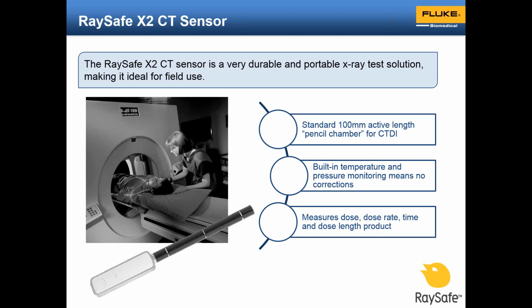A CT sensor is another option available with the RaySafe X2 system. Although commonly used by medical physicists for years to perform their annual surveys, this is not a measurement that most imaging engineers concern themselves with. However, with ever-increasing scrutiny on patient dose, this could be a tool an imaging engineer will need to use in the future. The X2 CT sensor is a standard 100 millimeter active length pencil chamber for making CT dose index, or CTDI, measurements. It fits directly into a standard head or body phantom, or can be easily positioned free in air with the included X2 Flexi stand.